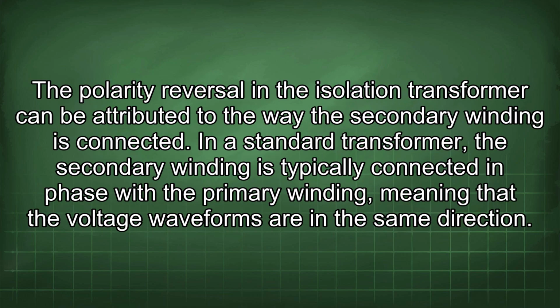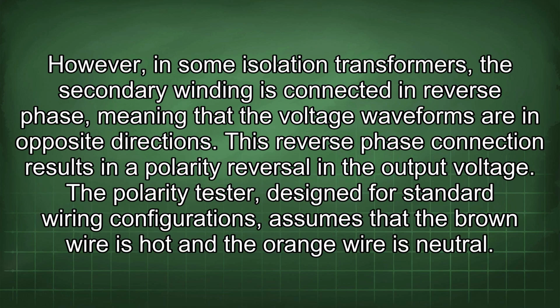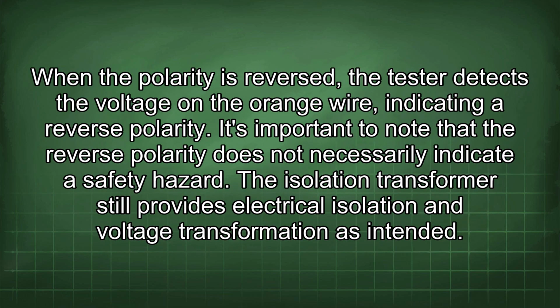The polarity reversal in the isolation transformer can be attributed to the way the secondary winding is connected. In a standard transformer, the secondary winding is typically connected in phase with the primary winding, meaning that the voltage waveforms are in the same direction. However, in some isolation transformers, the secondary winding is connected in reverse phase, meaning that the voltage waveforms are in opposite directions. This reverse phase connection results in a polarity reversal in the output voltage. The polarity tester, designed for standard wiring configurations, assumes that the brown wire is hot and the orange wire is neutral. When the polarity is reversed, the tester detects the voltage on the orange wire, indicating a reverse polarity.